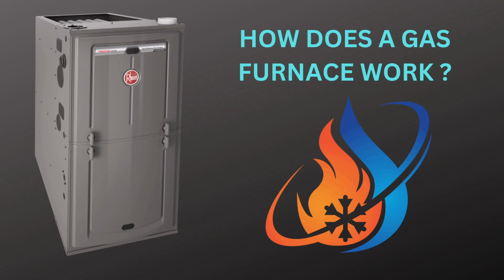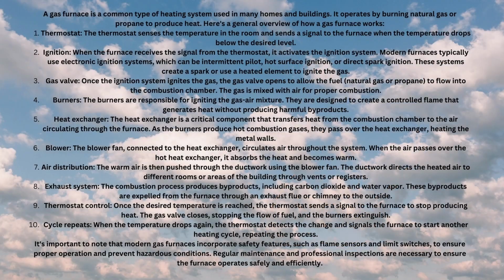But let's go over what is the gas furnace. Well, a gas furnace is a common type of heating system used in many homes and buildings. It operates by burning natural gas and/or propane to produce heat. Here's a general overview of how a gas furnace works. The thermostat. The thermostat senses the temperature in the room and sends a signal to the furnace when the temperature drops below a desired level.